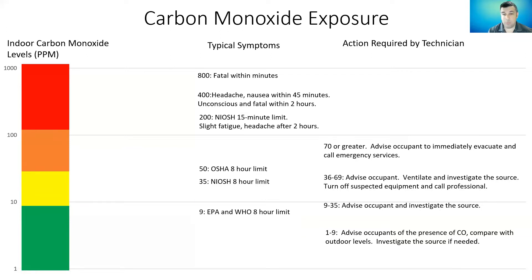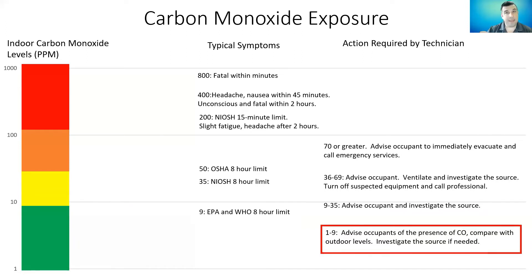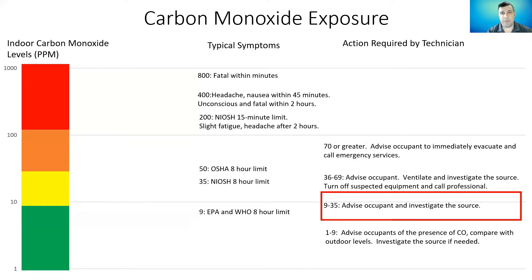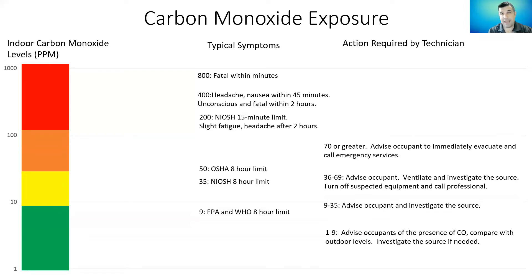At one to nine parts per million, it's best to advise the occupants of the presence of carbon monoxide and compare it with outdoor levels — maybe in an urban setting that's what it is outside, but it really should not exceed nine outside. Above nine to 35 parts per million, we definitely need to advise the occupant and investigate the source — start looking at equipment that could be the cause. Because at 35, we have reached NIOSH's eight-hour limit, and anything above that for an eight-hour period is definitely hazardous to our health.